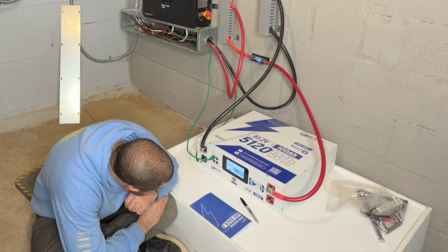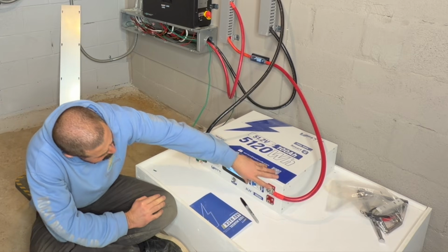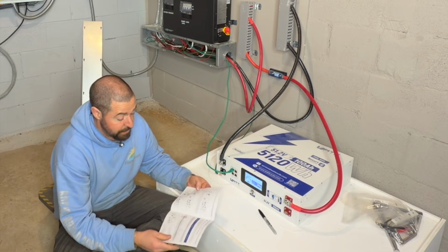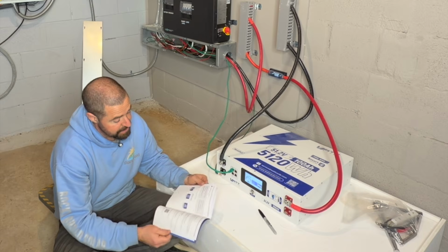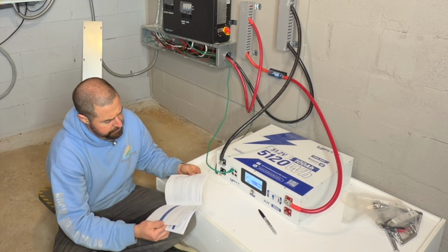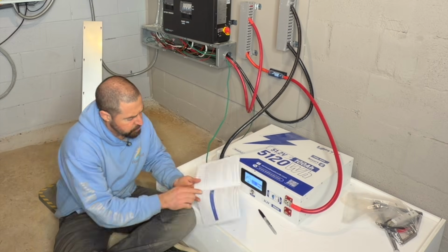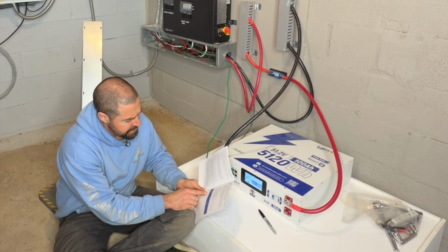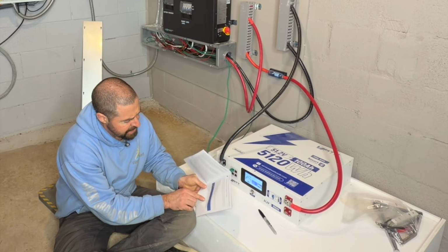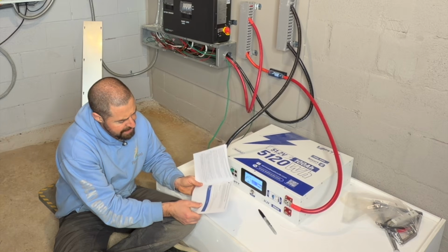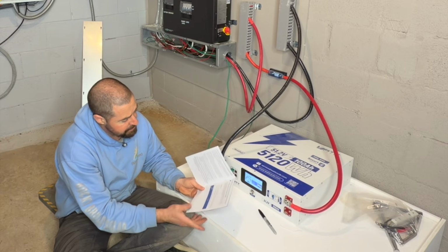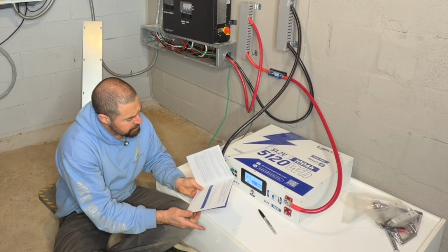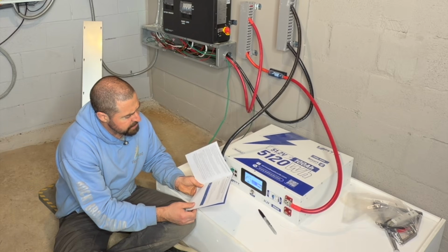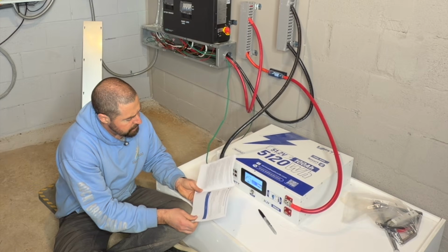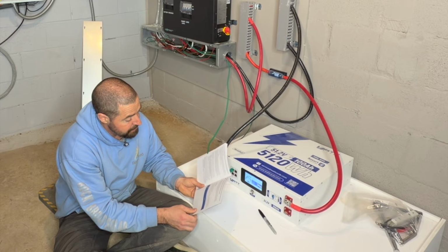I'm going to go ahead and just turn this circuit breaker on. Now, reading the manual here, it says the recommended charge current for one single battery is 20 amps, but it seems like it could go up to 50 amps. So at 20 amps, you've got a 5-hour charge time. At 50 amps, you've got a 2-hour charge time. But it's saying the recommended charging current is 20 amps. My guess is that's to maintain the lifespan of the battery.